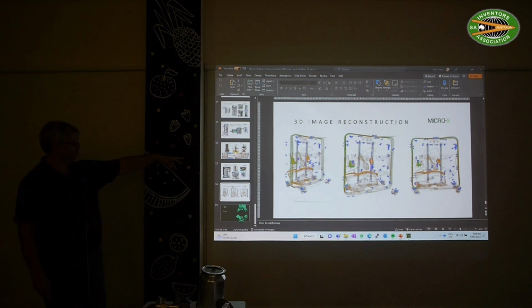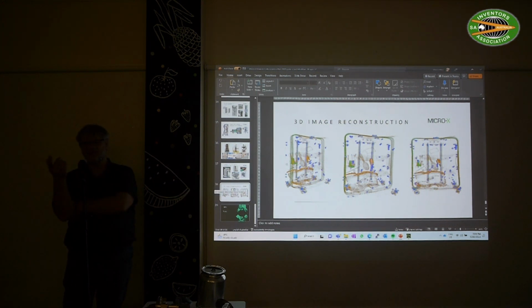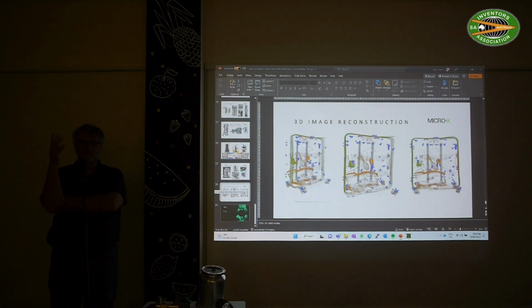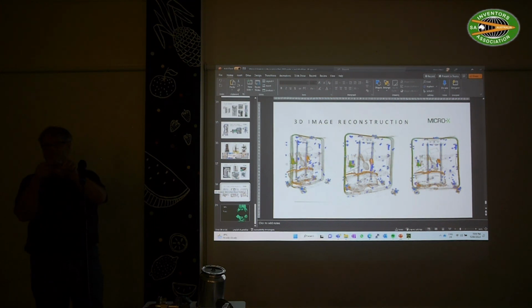The same thing with this baggage scanning machine. I think I mentioned to somebody, there's some weird language in some of the standards where they say if the door opens, you need to mechanically or physically remove a piece of wire from the circuit to power it off. So even a super duper industrial safety standard switch is not good enough. You need a switch, and we found one, that is a little metallic bridge that pushes into something to make the contact, and when it's removed, you physically remove part of the circuit in order to meet the requirements.